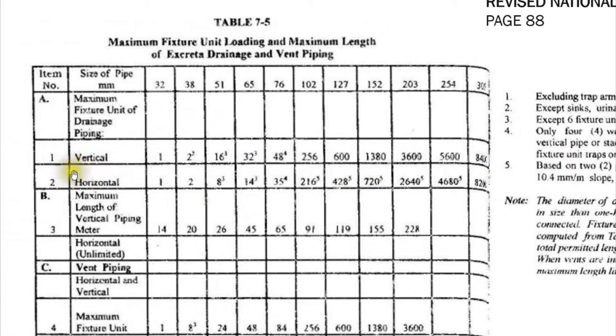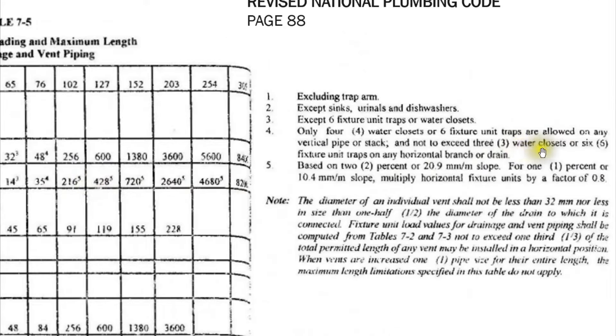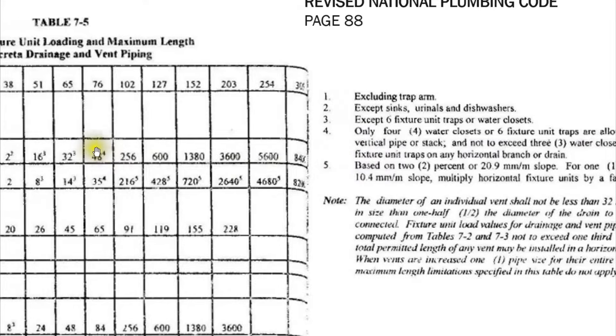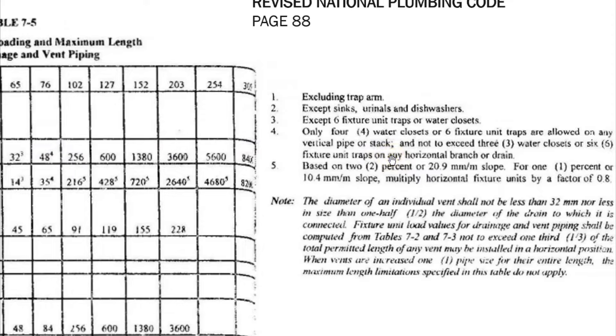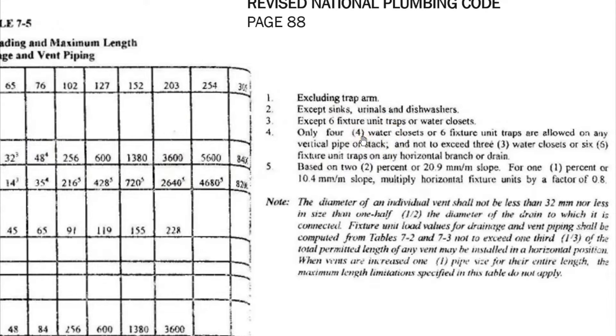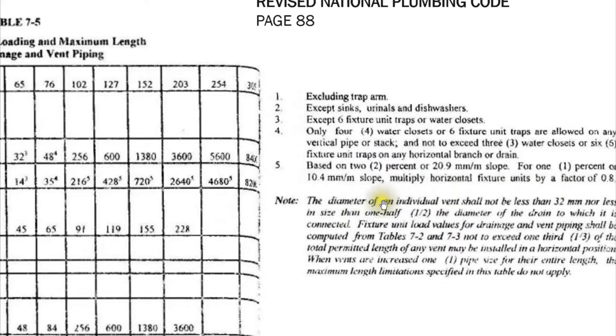For the horizontal pipe, the number of water closets connected should not exceed three — meaning no more than three fixtures with a drainage fixture unit of six. So remember: if your fixture unit has a superscript of 4, count the number of water closets connected to that pipe. If it is more than four, move to the next higher value for vertical pipe. If it is more than three, move to the next higher value for horizontal branch.